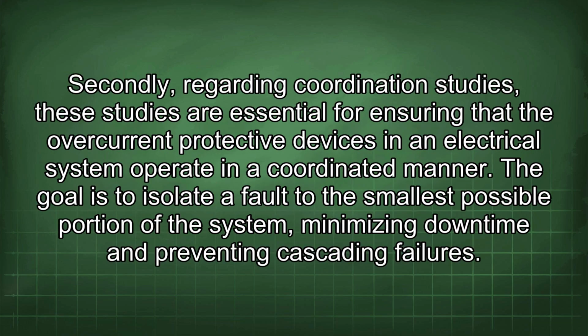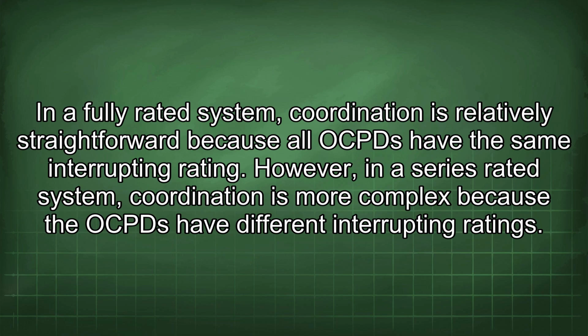Secondly, regarding coordination studies, these studies are essential for ensuring that the overcurrent protective devices in an electrical system operate in a coordinated manner. The goal is to isolate a fault to the smallest possible portion of the system, minimizing downtime and preventing cascading failures. In a fully rated system, coordination is relatively straightforward because all OCPDs have the same interrupting rating. However, in a series-rated system, coordination is more complex because the OCPDs have different interrupting ratings.